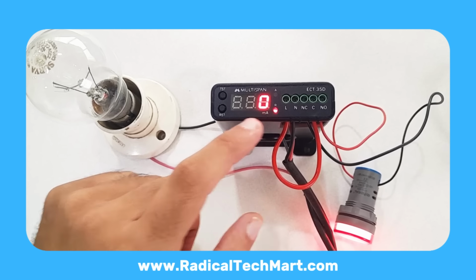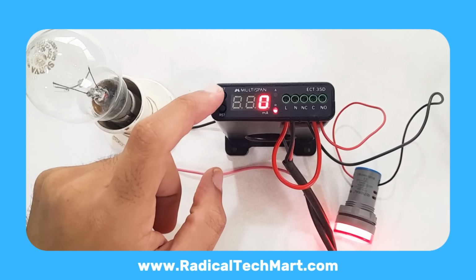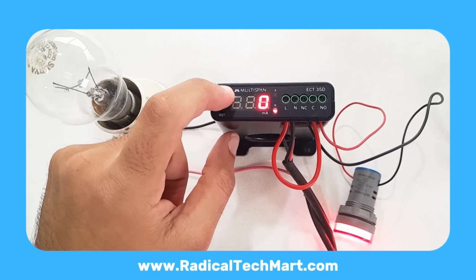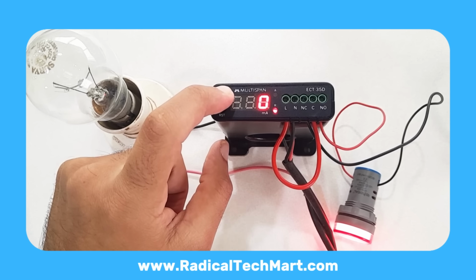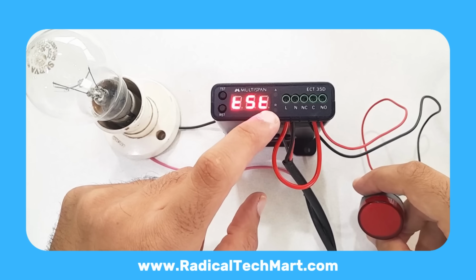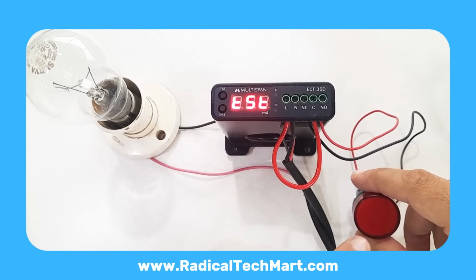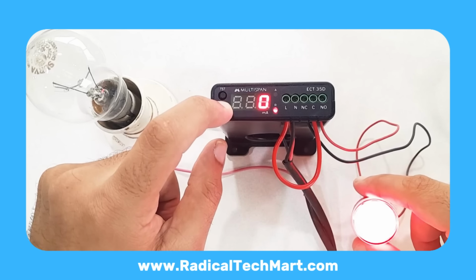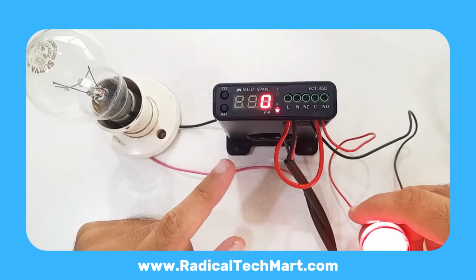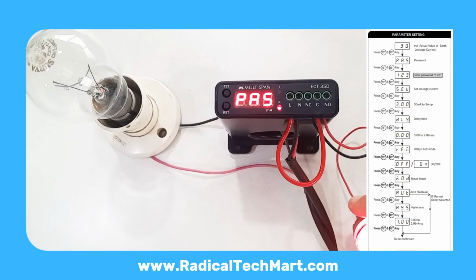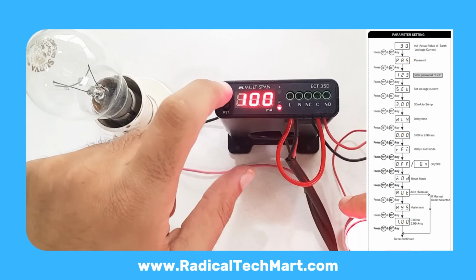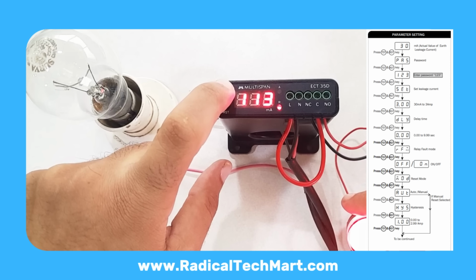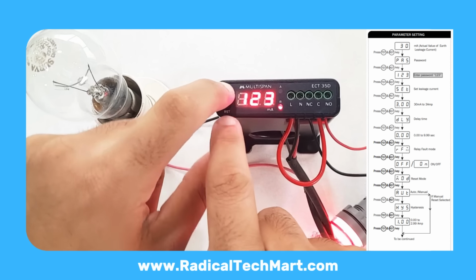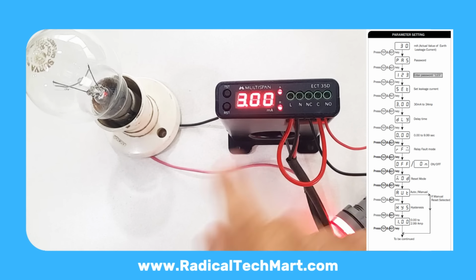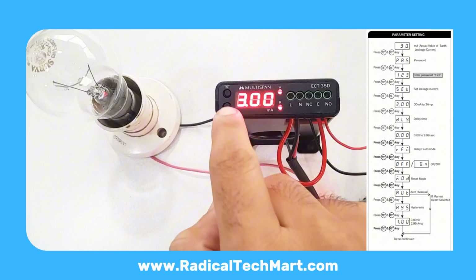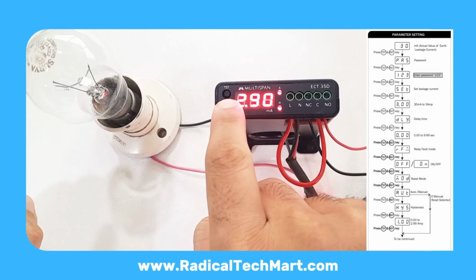We again have two buttons, test and reset. To check whether the relay output is working properly, press and hold the test button for 5 seconds. The display will show test, and the relay output will switch off. To bring it back, press and hold the reset button, and the system will reset. Now, to enter the settings menu, press both the test and reset buttons together. The display will show pass, asking for a password. The password is 123. After entering 123, press both buttons together again to enter the parameters.